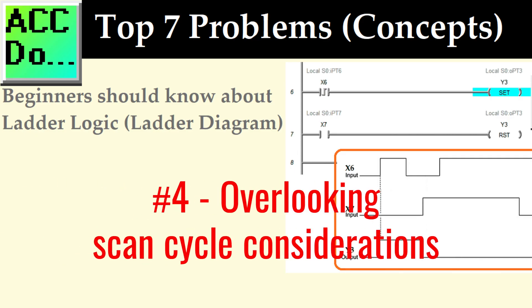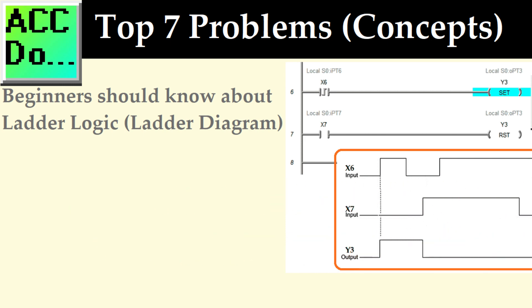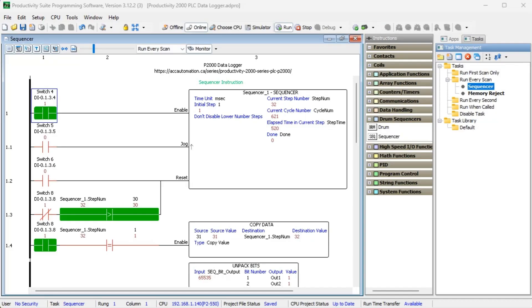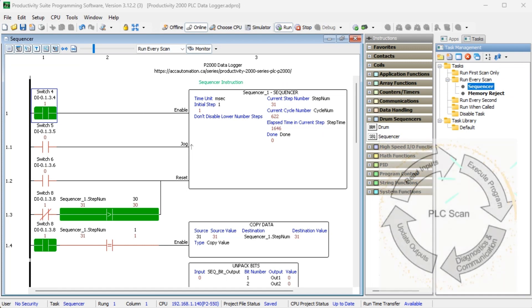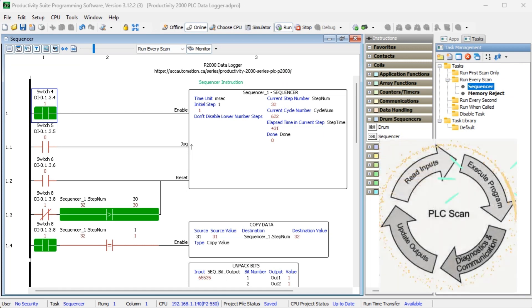Number four, overlooking scan time considerations. PLCs execute their programs in scan cycles, where the entire program is scanned repeatedly or cyclically. Beginners may not fully understand the implications of the cyclic nature leading to logic conflicts, race conditions, or undesired outputs.